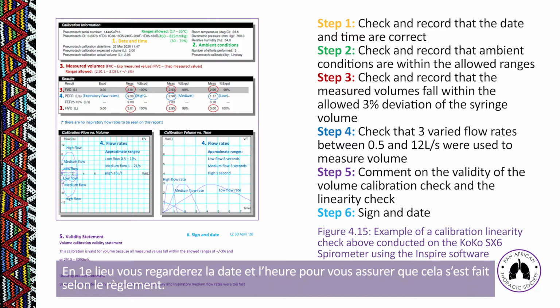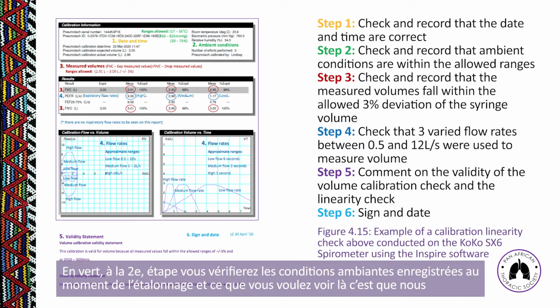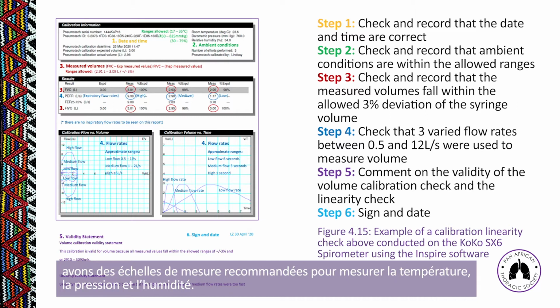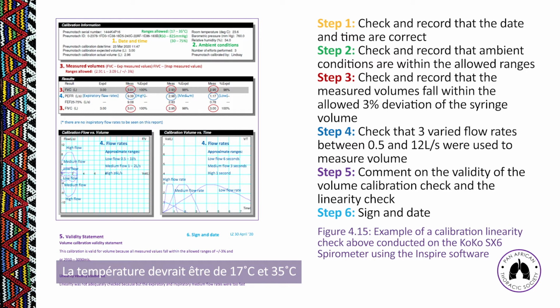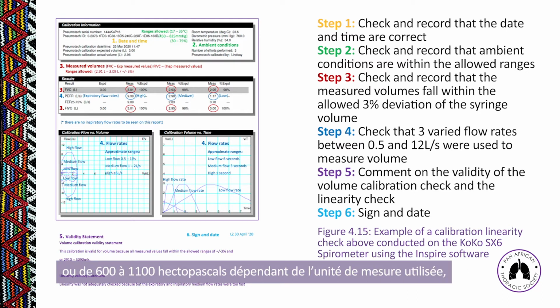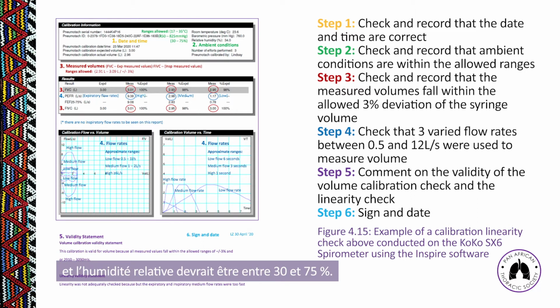First and foremost, you will look at the date and time to be sure that this has been correctly documented. In the green, in number 2, you'll look at the ambient conditions recorded at the time of calibration. And what you'll see there is that we have recommended ranges for temperature, pressure, and humidity. The temperature should be within 17 to 35 degrees Celsius. The barometric pressure within 450 to 825 millimeters of mercury, or 600 to 1,100 hectopascals, depending on the unit of measurement that you're using. And the relative humidity should be between 30 to 75%.